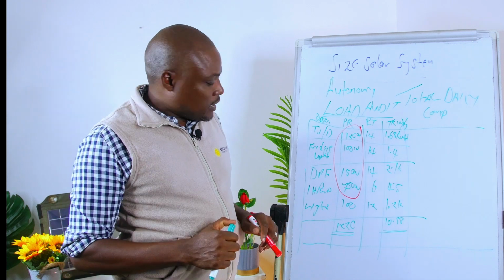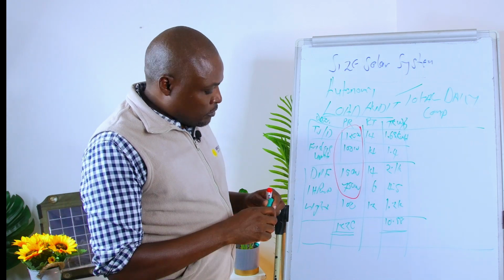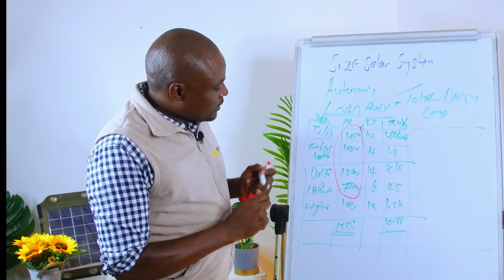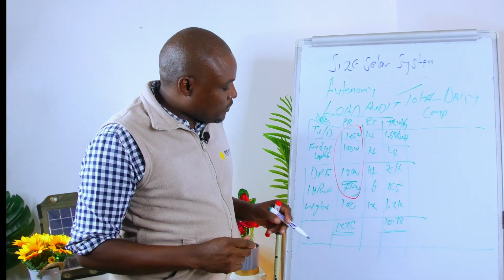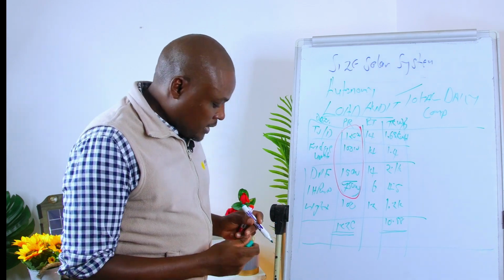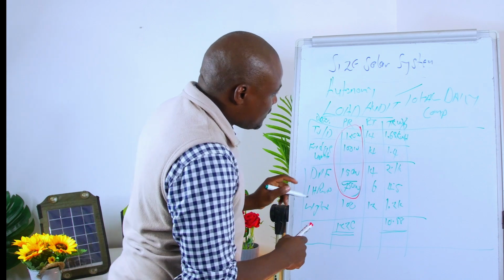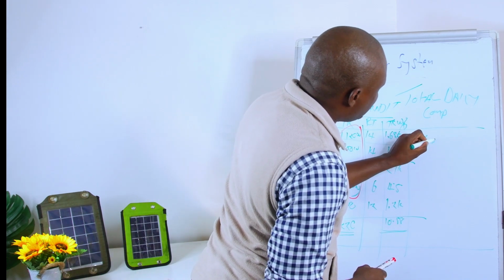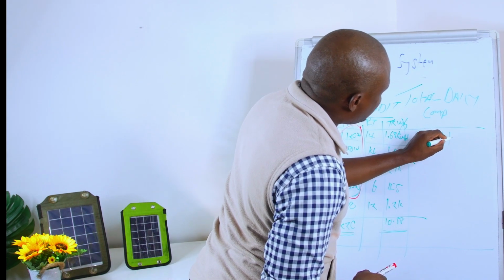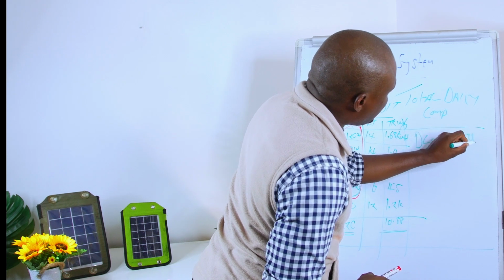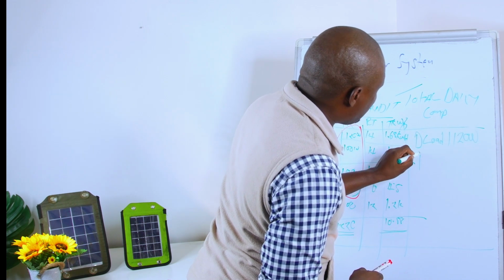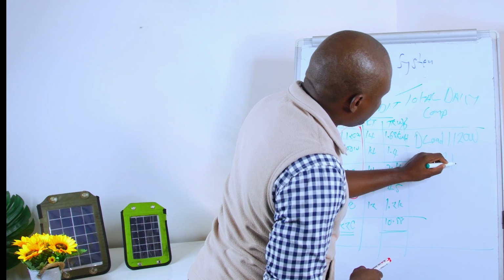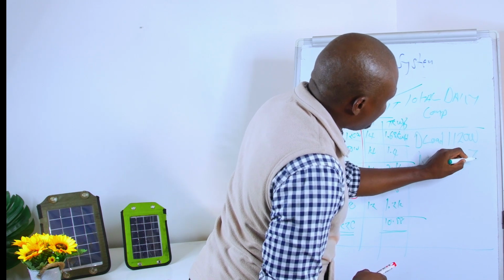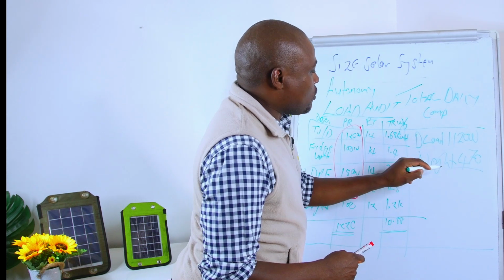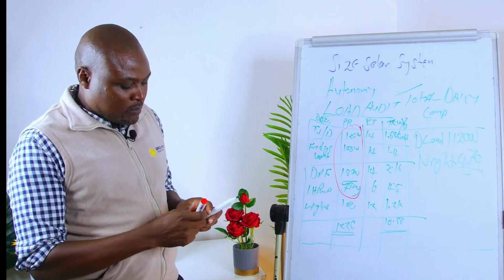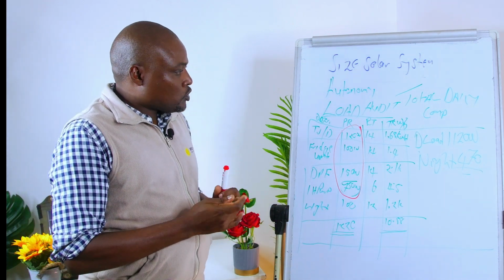Then the load for the night is the remainder after we've removed the pump. So once you remove the pump, the day load is 1120 watts, and the night load is 470 watts. So basically what it means is that you want to size a system that is able to power this load for the next 8 hours during the daytime.